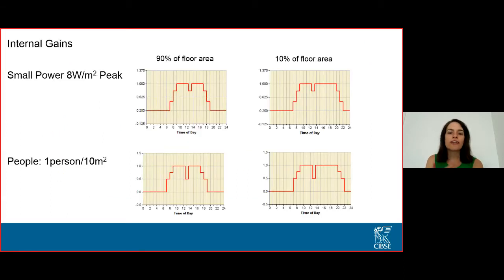Within the model, we looked at what is a realistic small power target for offices. This is data driven, using data from operational offices we can identify, showing 8 watts per metre squared is actually achievable in offices in London now. We've applied that to 90% of the floor area operating during the standard 8 AM to 6 PM period, plus an extended operating period for the 10% of floor area in offices that tend to run longer hours.